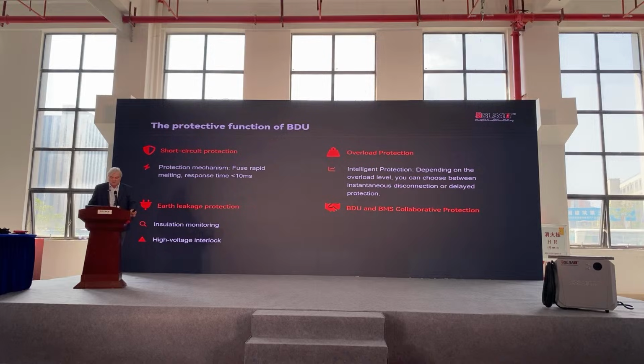For the protective functions of the BDU, we get short circuit protection, with protection mechanisms for the fuse and a rapid melting response time of less than 10 milliseconds. We've got earth leakage protection, so insulation monitoring and high voltage interlock. We get overload protection, so that with this intelligent protection, depending on the overload level, you can choose between instant disconnection or delayed disconnection, depending on how you want to do it. And now we've got a BDU and BMS collaboration that comes into one unit.